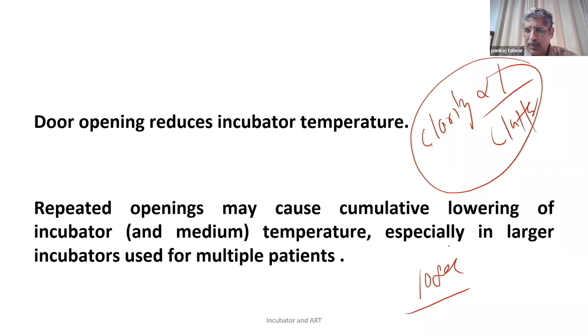So repeated openings may cause cumulative lowering of the temperature and the CO2. This is important. Strict temperature monitoring and control is advisable. Similar precautions and concern about CO2 levels and humidity I've already covered for you. Loss of humidity will occur when we open the incubator and hot humid air comes out. Can someone tell me the humidity in the IVF lab? 40 to 50%. And in the incubator? More than 90, 95%.